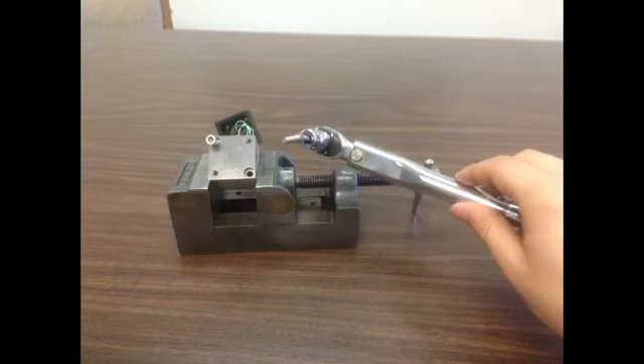If the reading is greater than 100 kilohms the sensor will probably work. A reading below 100 kilohms means there has been a breakdown in the isolation between the coil wires and the metal case. This often causes drift or noisy pressure readings from the sensor.